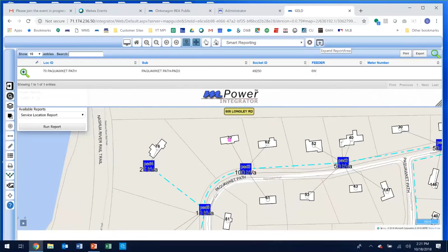I've zoomed into this service location where you can see several pad-mounted transformers. I'll use the trace capability, which is based on the circuit model. You'll notice different traces he set up for different purposes: trace down, trace up to the first protective device. Here I'll select flood to protective device, and the software floods upstream and stops at a particular fuse in the corner, a 75 kVA fuse. Now he can run reports based not just on an individual transformer, but on the whole load on that fuse, checking his fusing throughout the system.